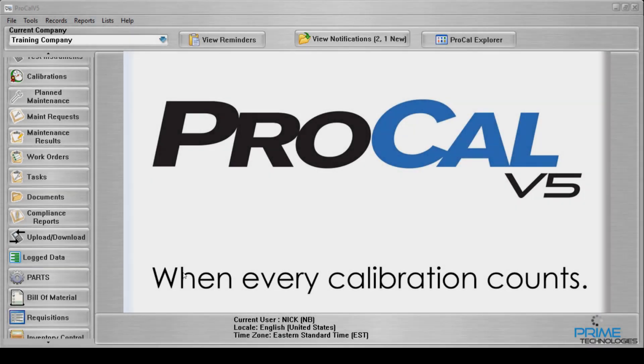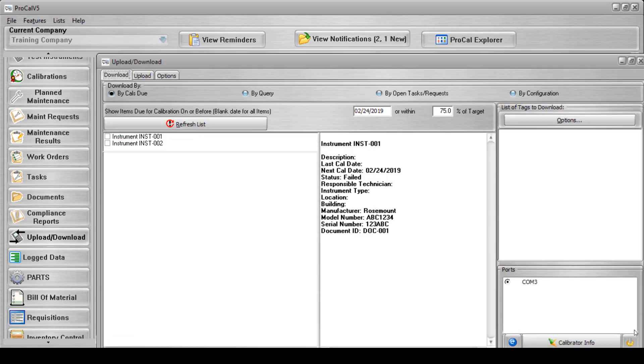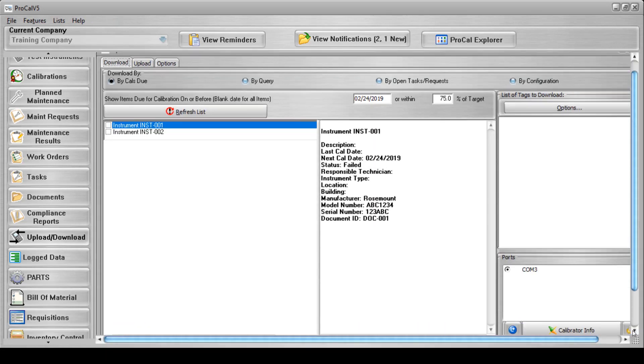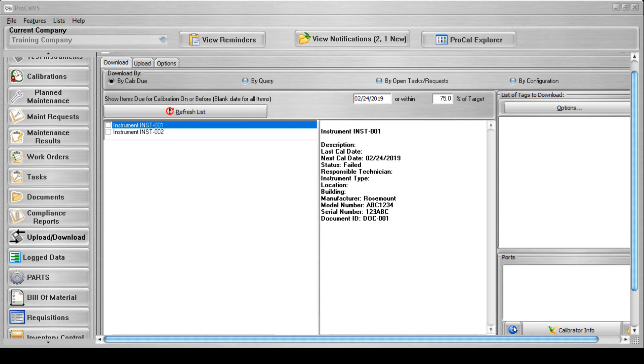The second way a user can perform a calibration in ProCal V5 is to use the Field Calibrator Utility. To do this, the user must open the Upload Download screen and verify that the Calibrator is connected. Next, select the tag to be downloaded and then select the Initiate Download button.